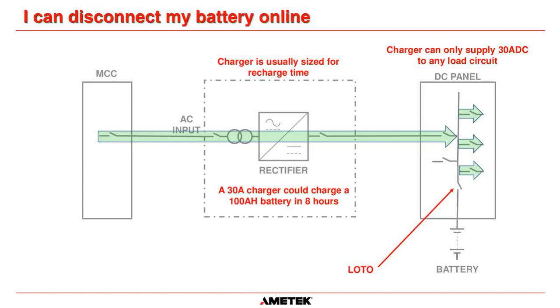Okay, so the rectifier should be loads and battery. Well, John, once again, if you go back to the start of my presentation, rectifier and battery charger are two interchangeable terms because they do exactly the same thing. The term rectification means changing AC into DC, and a battery charger changes AC into DC. So the differential is, for a rectifier, in truth, it wouldn't have a battery connected to it, but that's not the case because many rectifiers do have batteries connected to it, and people will just call it a battery charger. Am I rambling, or does that make sense? But you should always have this battery connected.